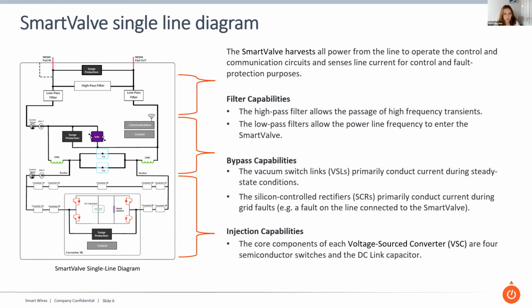You don't always want to be adjusting the impedance of your line. You may, in fact, want to only use this when you're in a post-contingency event or you have a particular overload. And so we use these vacuum interrupter switches, VSLs, to operate in what's called a monitoring mode or a bypass mode. And that gives the system operator the flexibility to not inject at all by closing the VSLs. And these provide a lower impedance path to the IGBTs, and we put the IGBTs in a blocking mode as well. And that prevents us doing any voltage injection. So it's almost like we're basically a short for the transmission line. The transmission line comes into the device, goes straight through the VSLs and straight back out again.